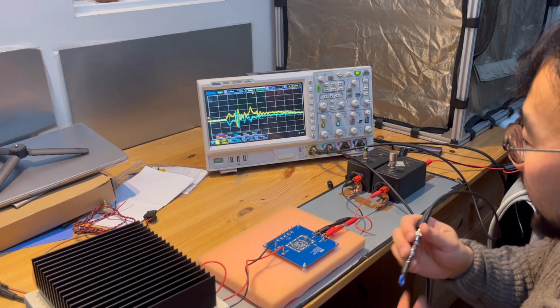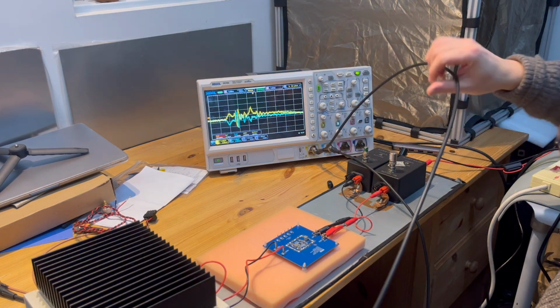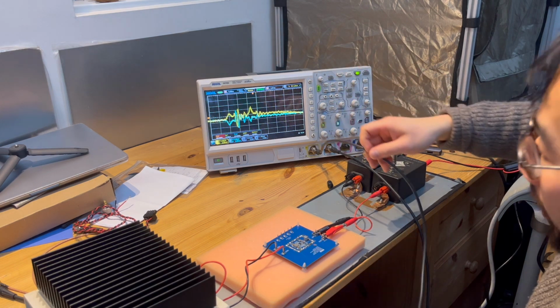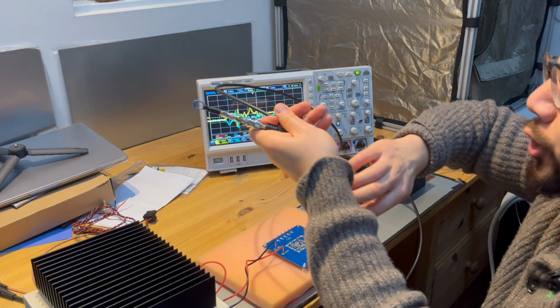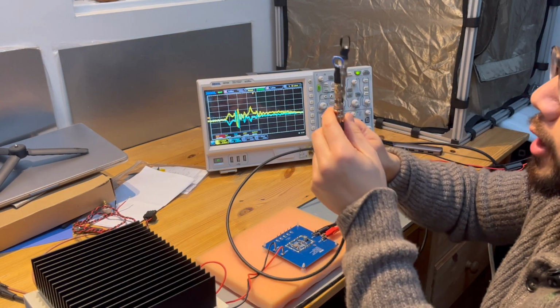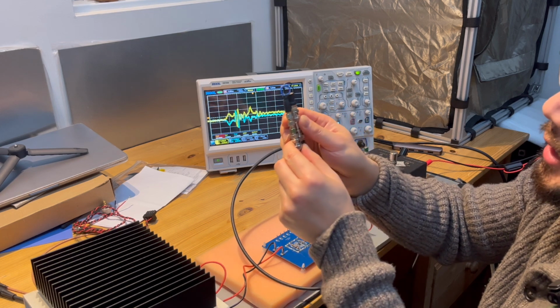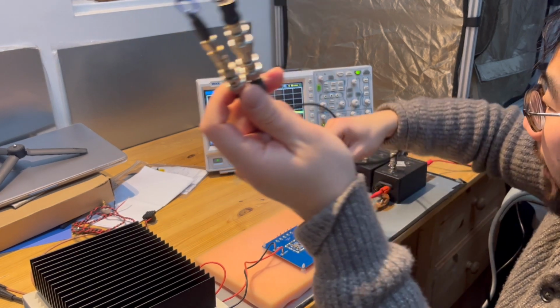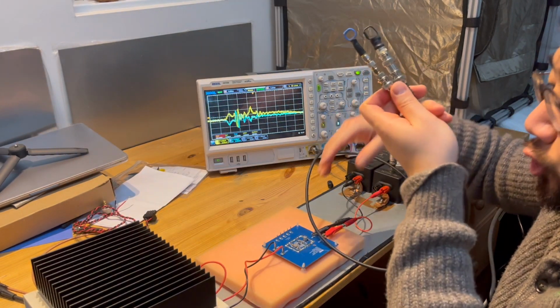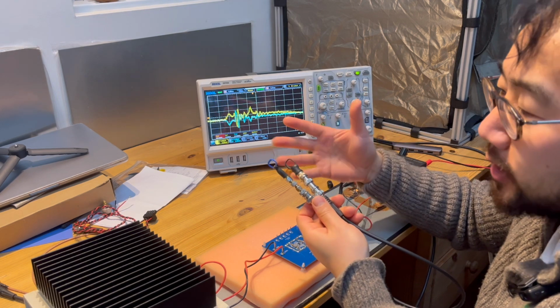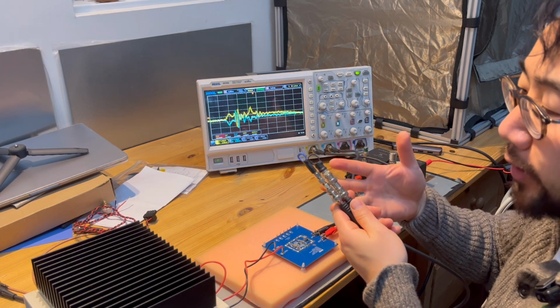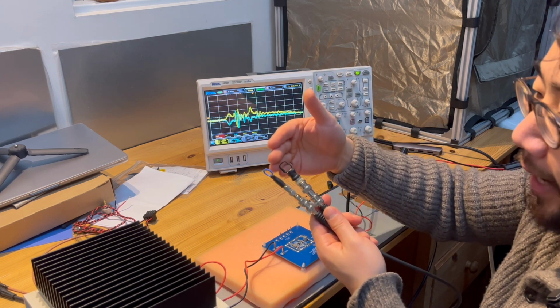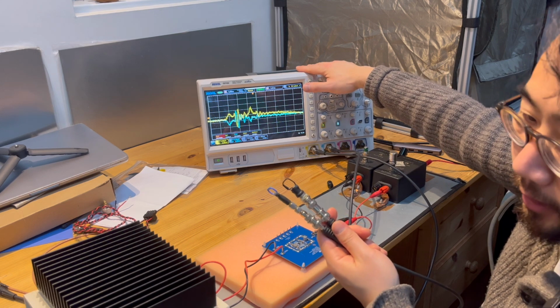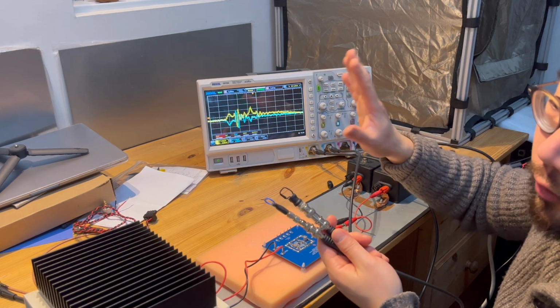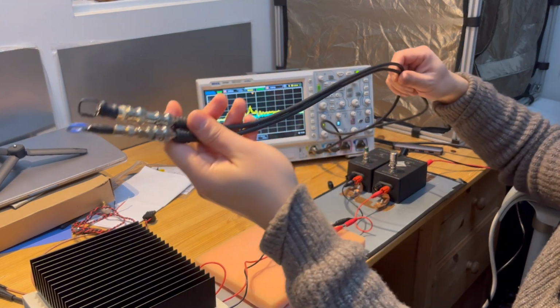Okay, so you can see we now have channel 1 and channel 2, and it's quite important to set this up correctly. First, you will see that we use two loops. If you look at the size of them, the sizes are not exactly the same. But we try to keep the length of the coaxial cable exactly the same. This is extremely important because we're dealing with very high frequency, high speed measurement. If you use different lengths of coaxial cable, then by the time the signal travels to the oscilloscope, you will have a slightly different phase shift between the two signals. So we try to keep the transmission line length as close as possible, okay?